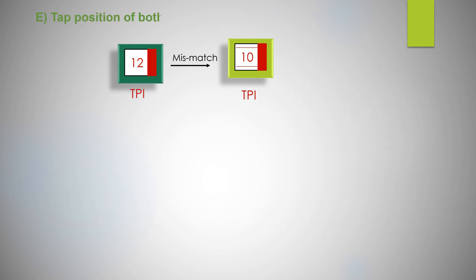Tap position of both transformers should be same. During tap changing, secondary voltage of both should be the same. At RTCC panel, master-follower arrangement should be incorporated to avoid any mismatch of tap position. Voltages at different taps are different.